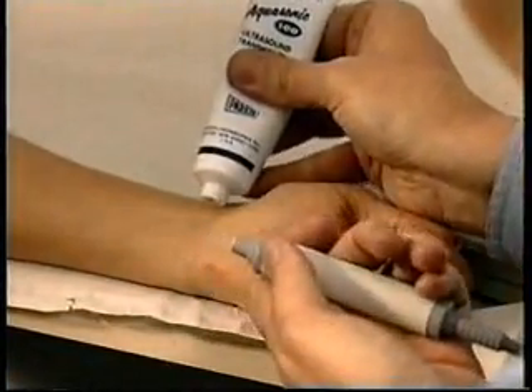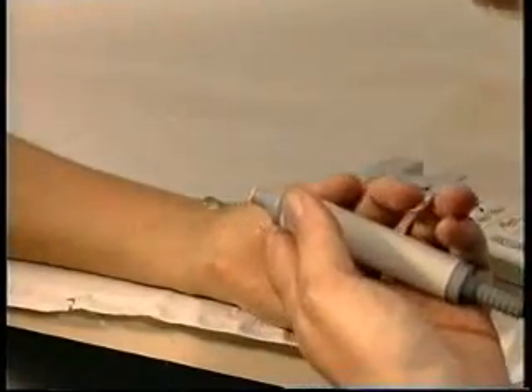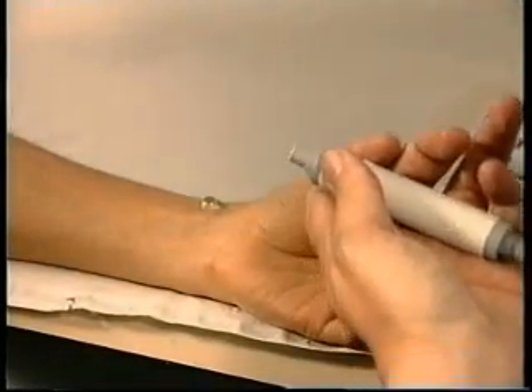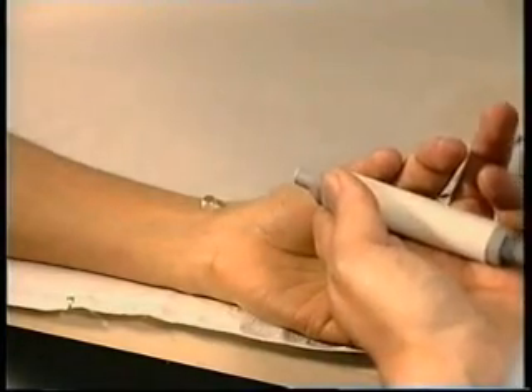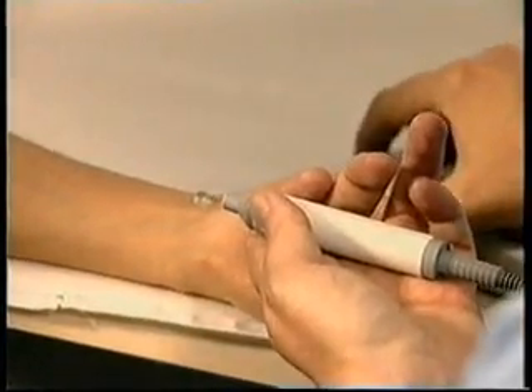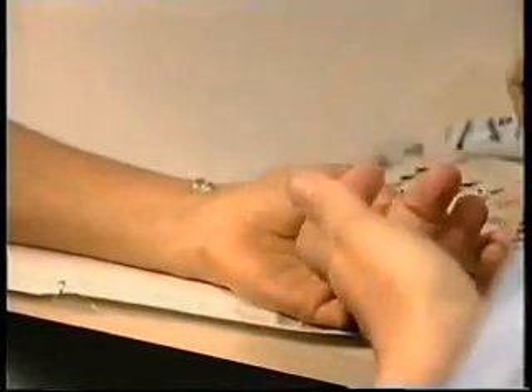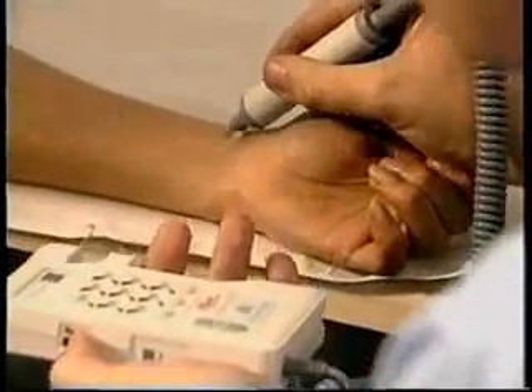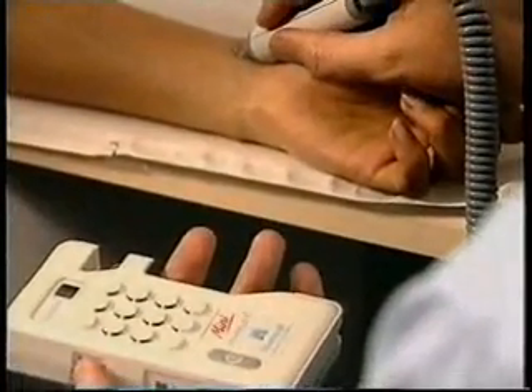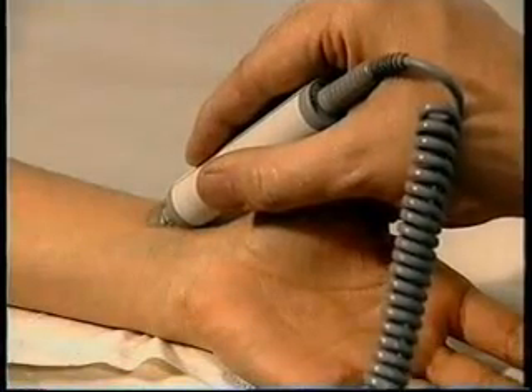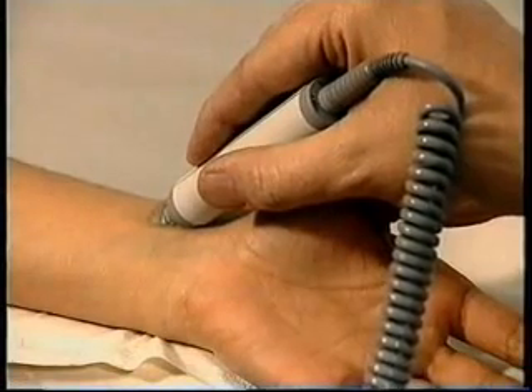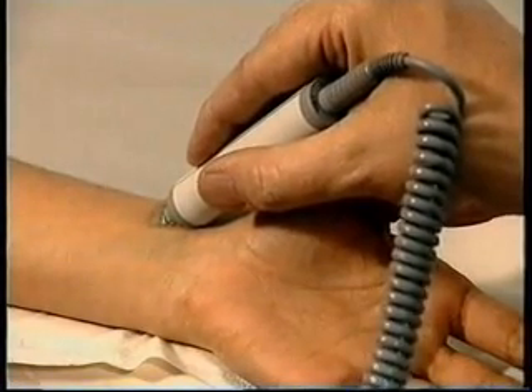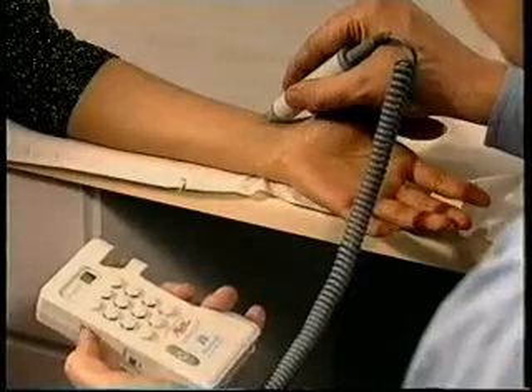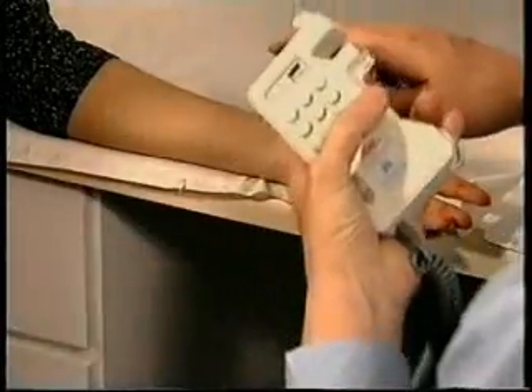We have to use some gel to exclude air from between the probe and the skin, and that's common with all other ultrasound techniques. The reason for it is that we have to exclude air because otherwise the sound will neither go into the body nor come out again. And what we now have to do is to align this probe so that it's pointing along the vessel. There it is. And when it is, we can hear a whooshing sound. And there's one whoosh for each of your heartbeats. But with this very simple piece of equipment, we can start to say something about the nature of the blood vessels in the body.